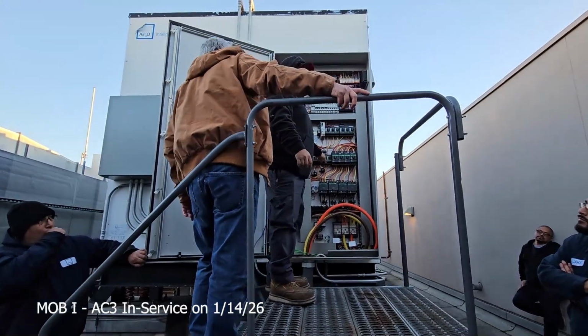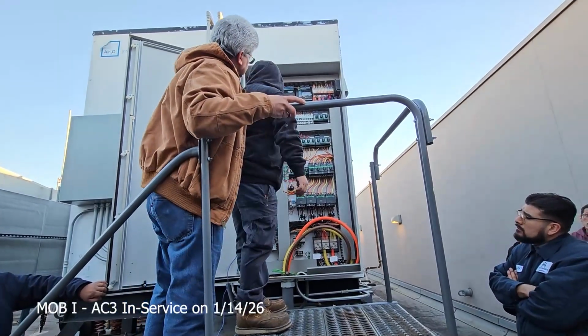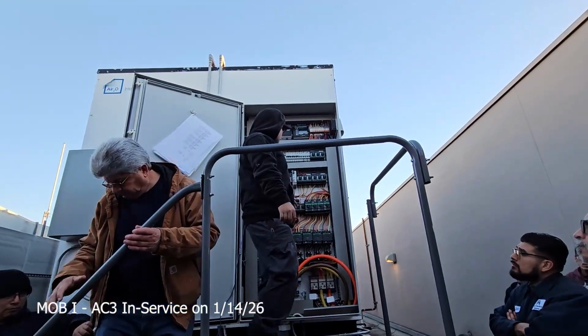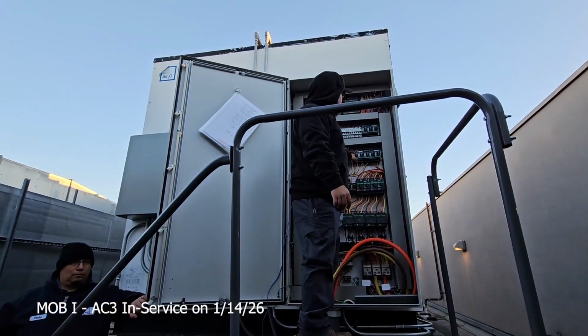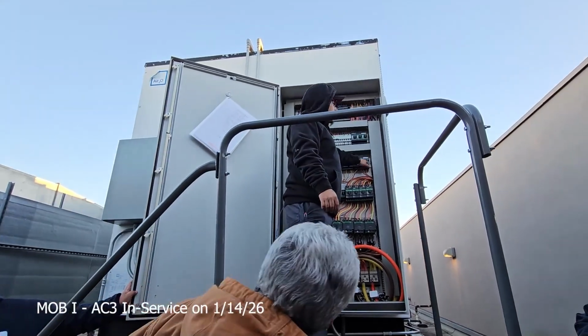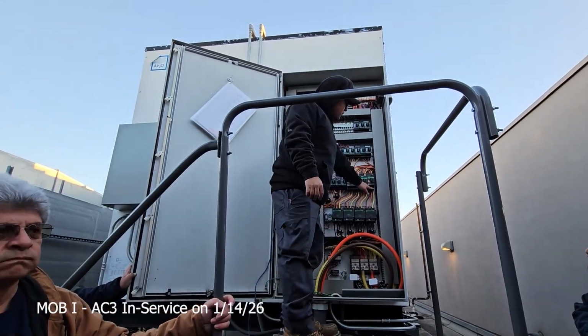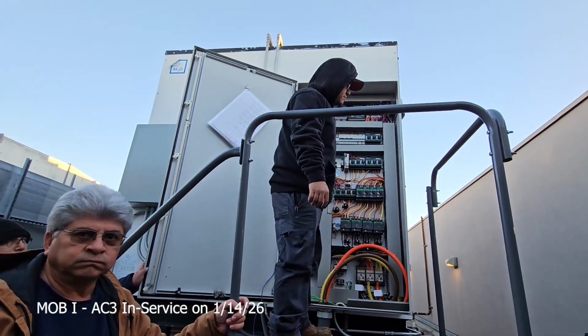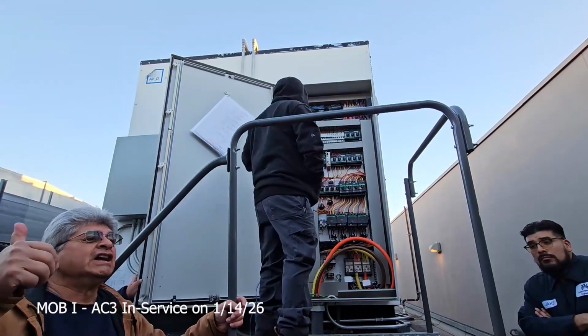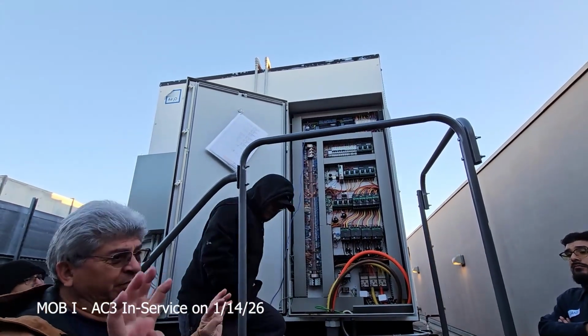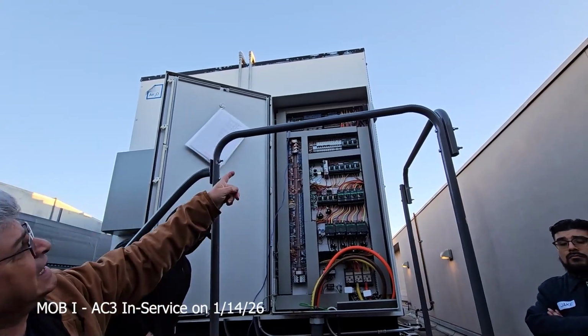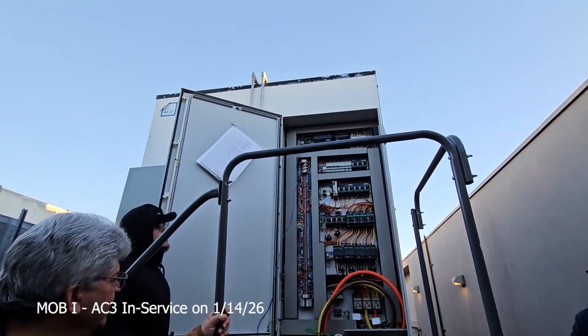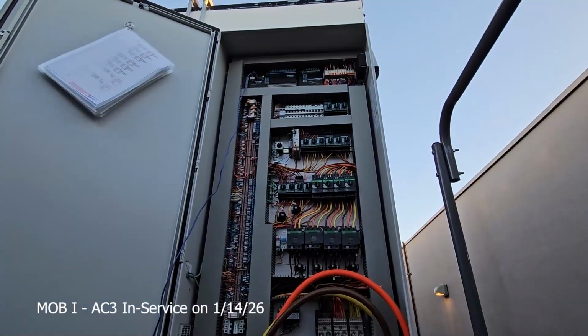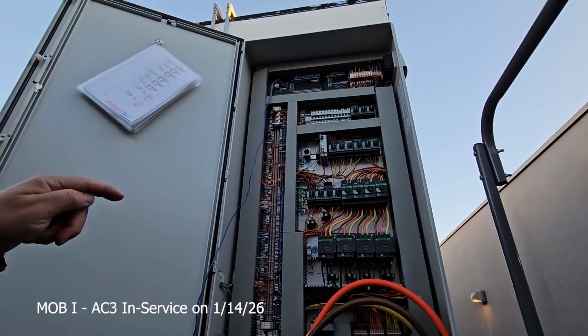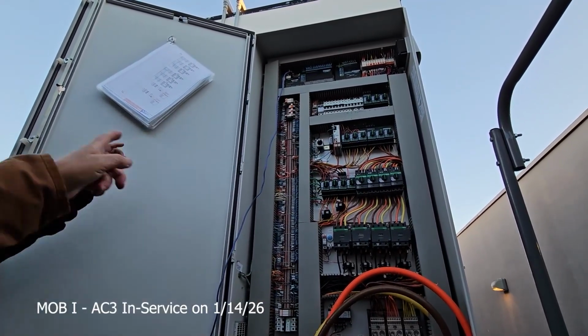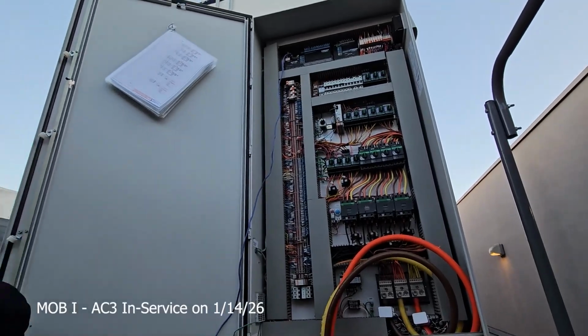Mostly right here, these are all your supply fans. These four, like Henry was saying, there's a wire diagram here that'll show you everything. For the most part, from what I can remember, these are your supply fans, 3 return fans, and your 6 axial fans right here, which are your condenser fans. And these will be all your compressors, of course, with your contactors right next to them. So 6 condenser fans, 4 supply, and 3 returns, and the little tiny guy up there. That's what you have for fans. They're labeled on the top. If you walk up top, you'll see the labels, and you can refer to them in the wiring diagram. Okay, thank you.